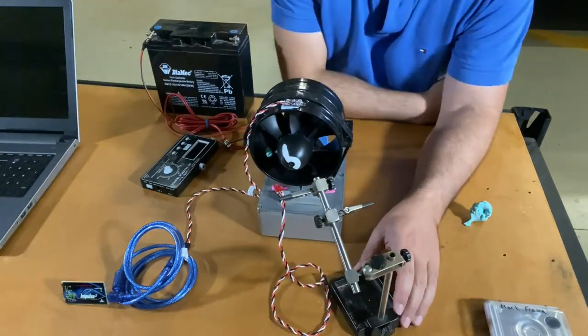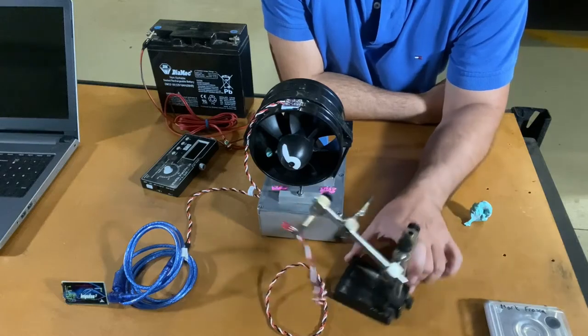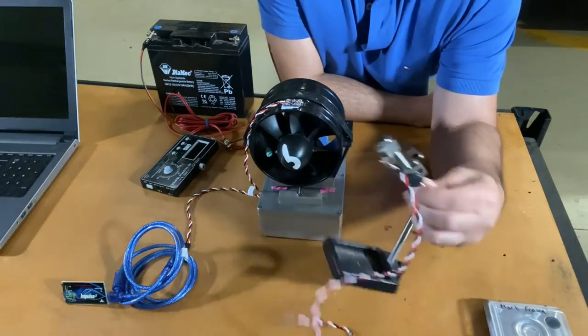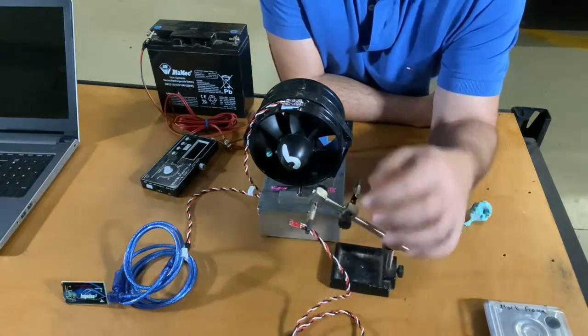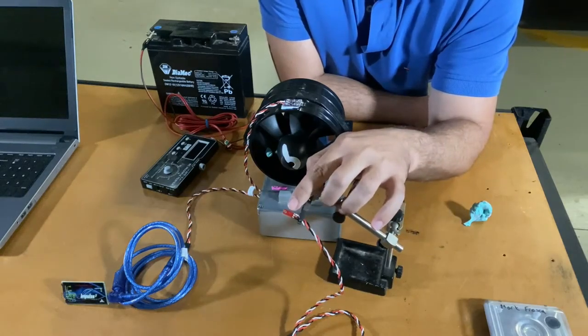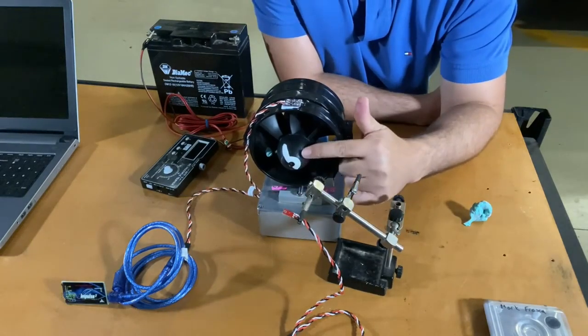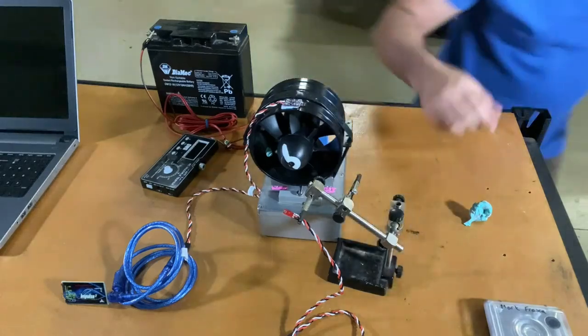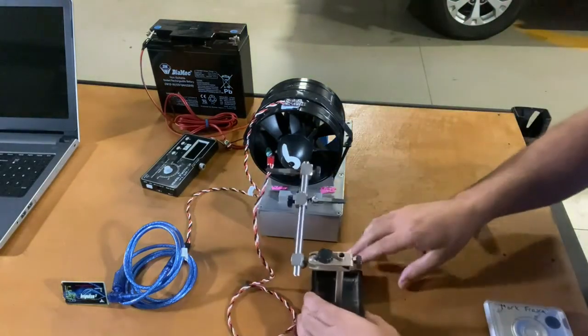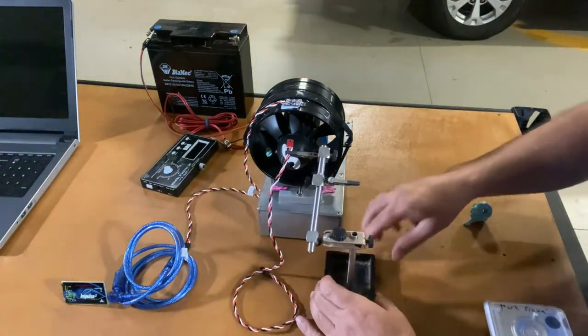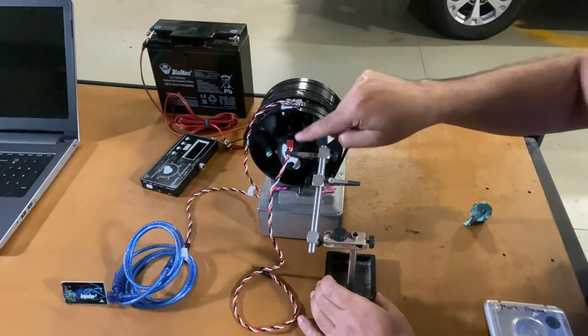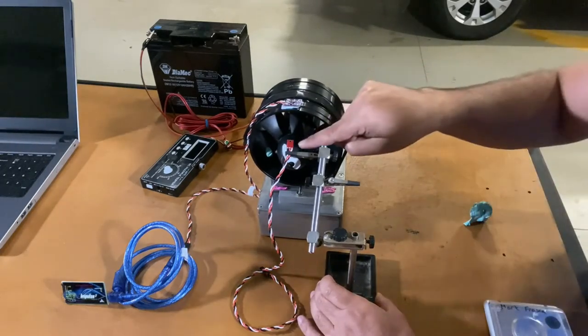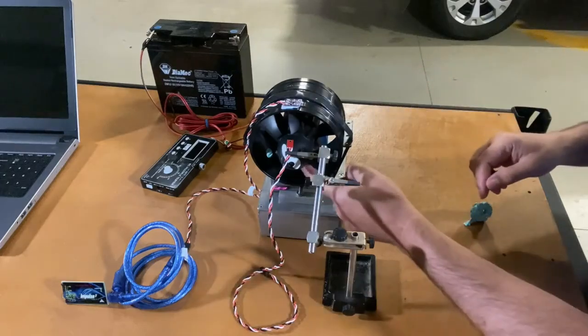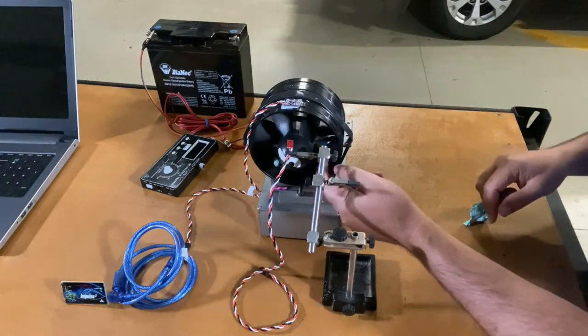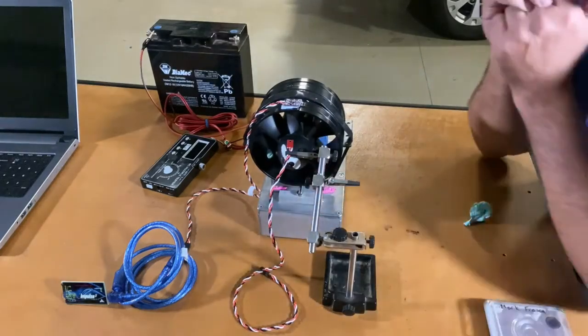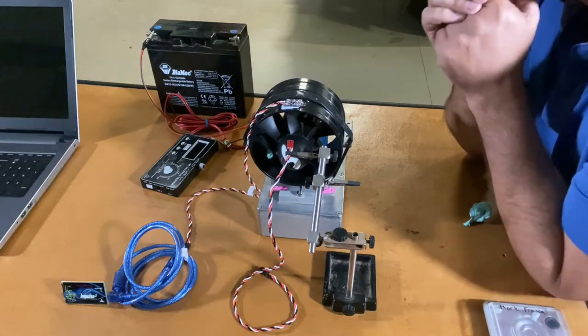So when I install the infrared sensor, it has a very short range. The range is normally between 3 and 5 millimeters from the hub of the impeller. So when I install that, I like to install it so that it is normal to the hub and not too far away, so that when the line passes the infrared sensor, it should give you a nice pulse signal on the screen.